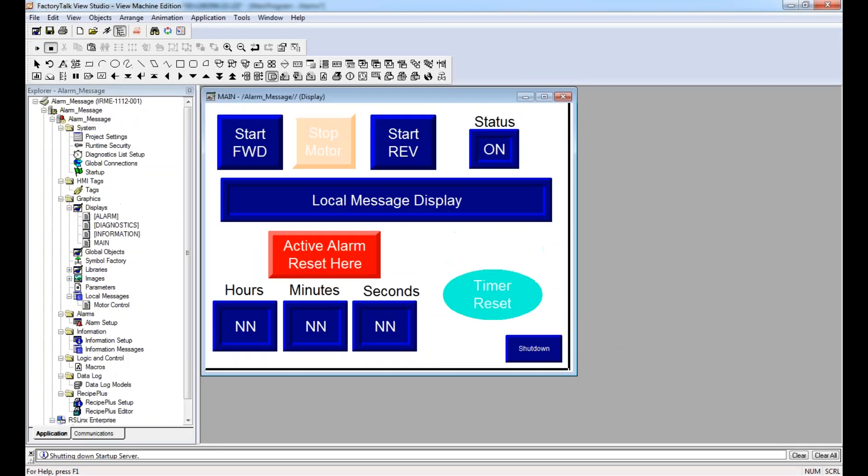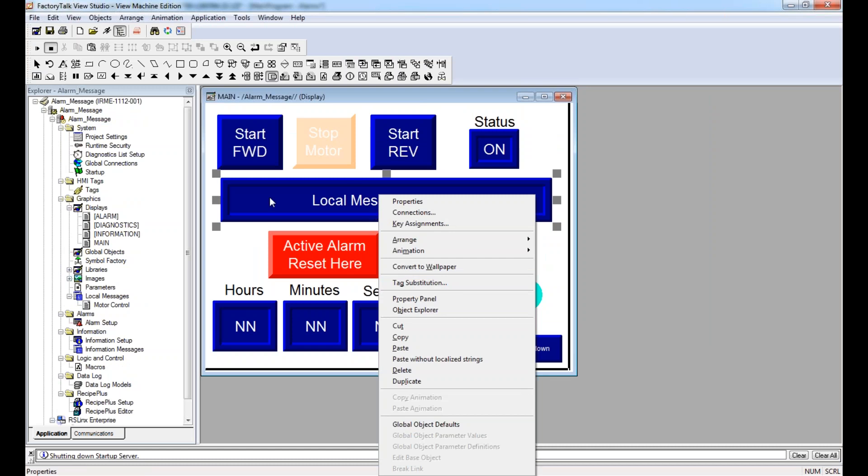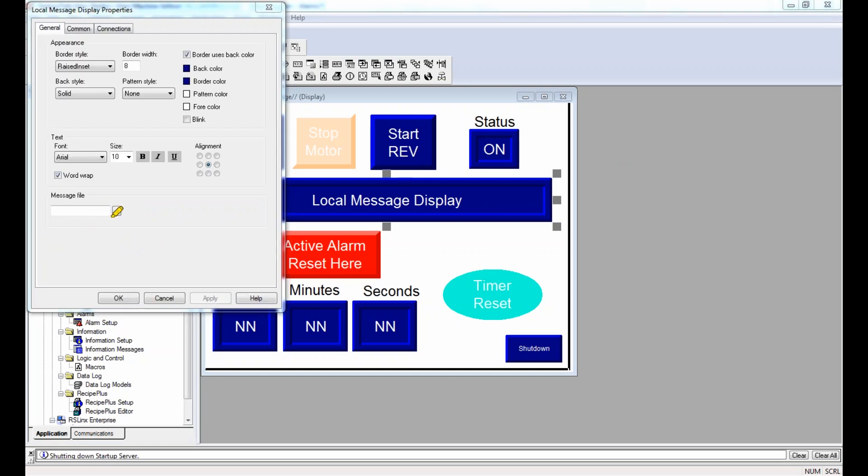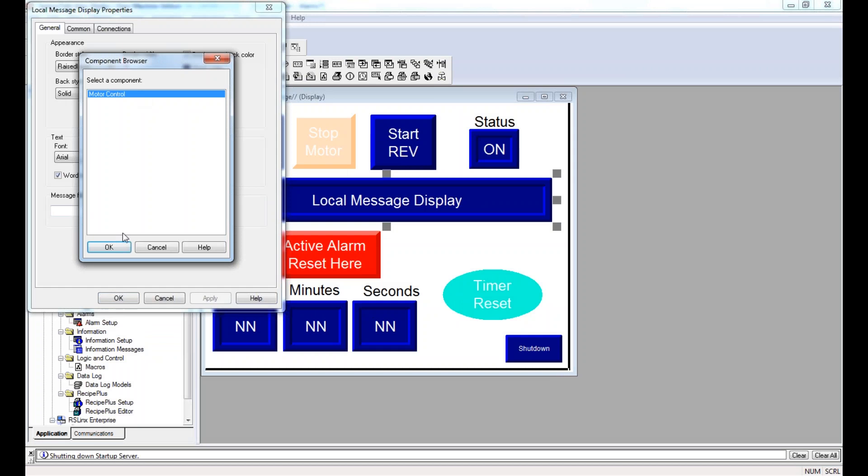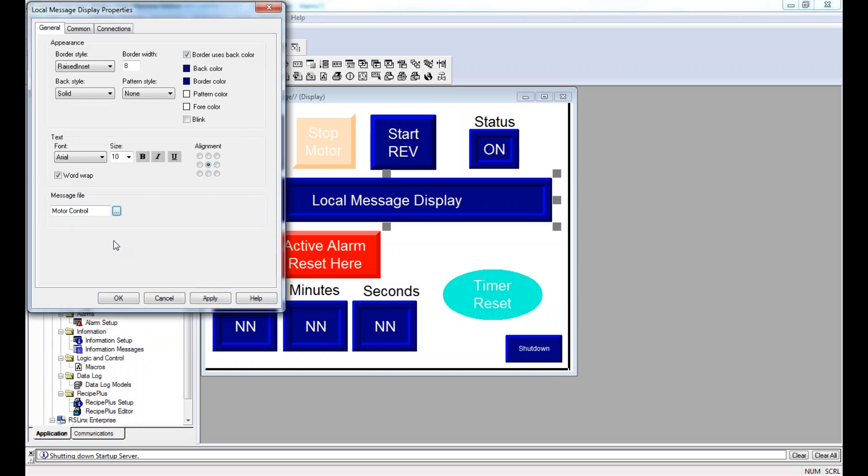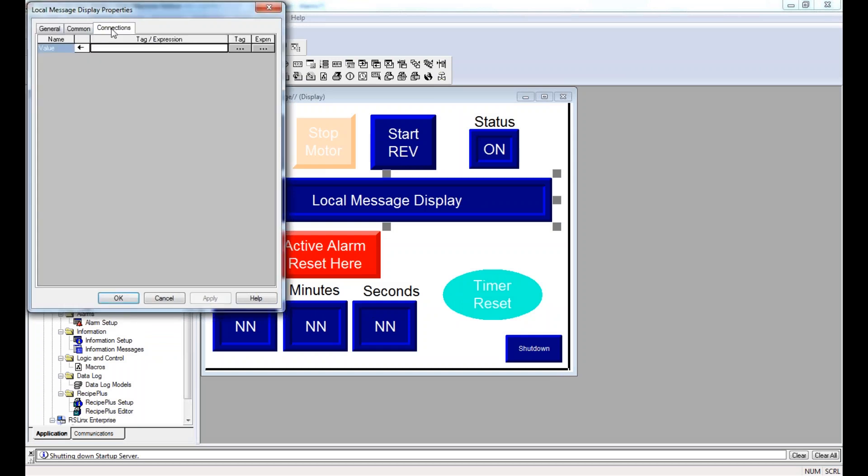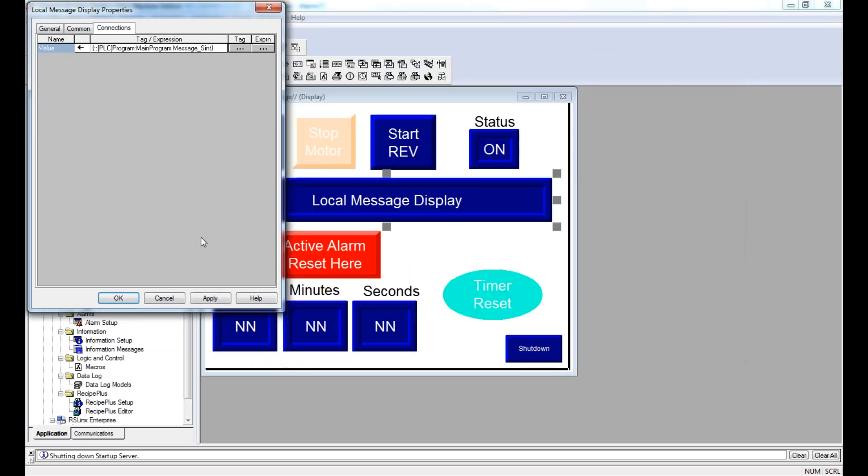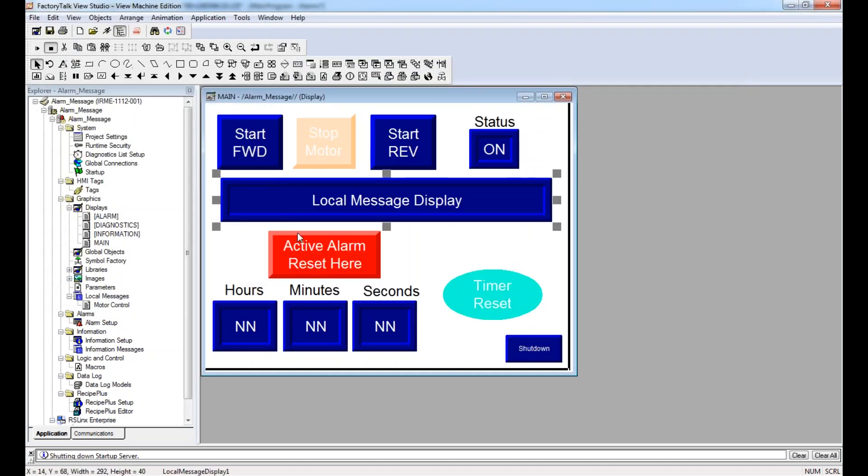So I hit close, and if I go into this local message, I will go into properties. And then here on message file, right down here under the general tab, this is where I link up my message file that I'm drawing from. I highlight it, highlight motor control, hit okay. And then I have to put a connection in as what value is going to trigger the change. And so here's my tags, and I'm going to go to message sent, because that's my message display. Hit apply, everything's hunky-dory, and there we go.